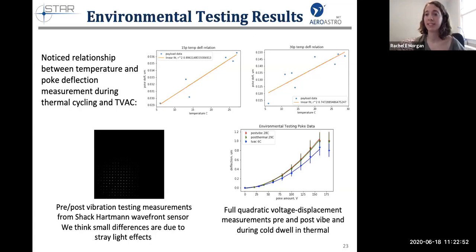Sure. The work is still ongoing. In my case, it has been really interesting to revisit the Zygo measurements, or the mirror actuator measurements, that we took before we installed the mirror into the payload. I've been working on characterizing the background noise in those measurements in order to really understand exactly how well we know the voltage response of each actuator, so that we can calibrate our Shack-Hartmann sensor and understand exactly how well that Shack-Hartmann sensor is measuring each actuator.